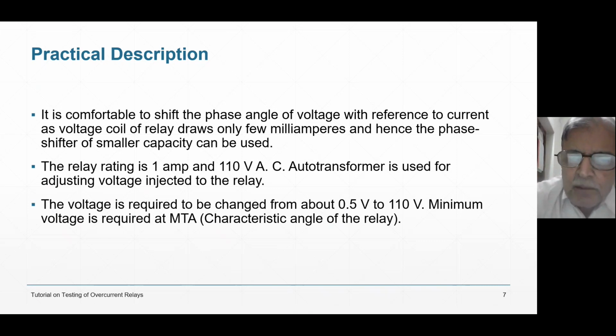The relay rating I am using is 1 ampere and 110 volt AC. The auto transformer is used for adjusting the voltage, which needs to be changed from roughly 0.5 volt, because of the directional sensitivity. Sensitivity means the minimum voltage at which the relay operates, usually 1%. So for 110 volts, I need 1.1 volt. If I can set 1.1 volt, that is enough. But I'm trying to measure from 0.5 to 110 volt, more than enough.